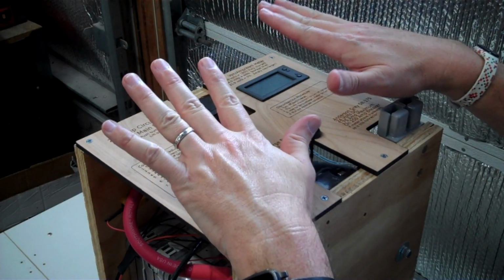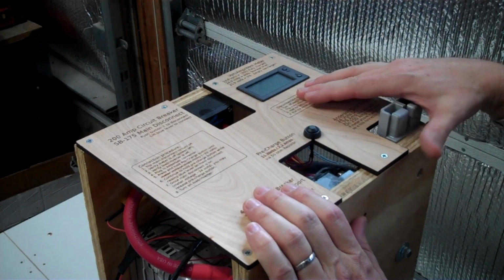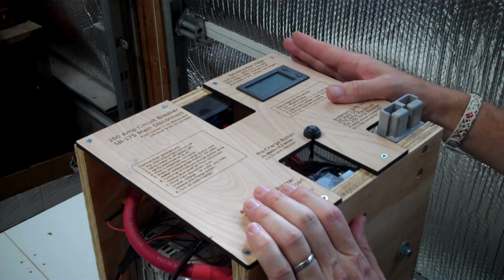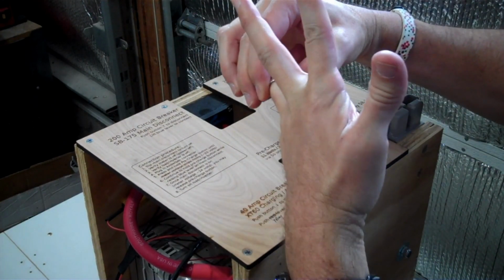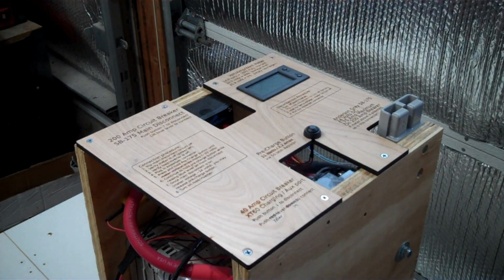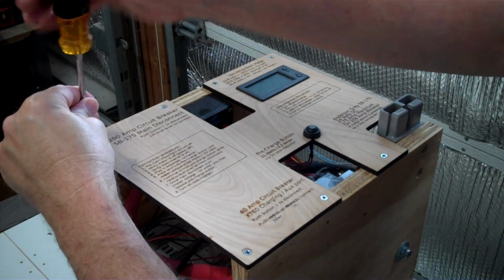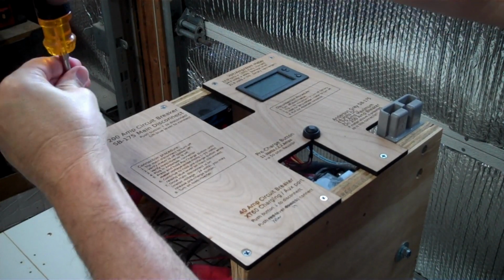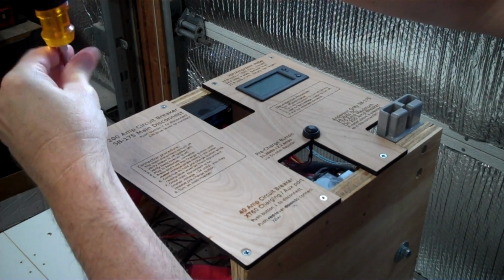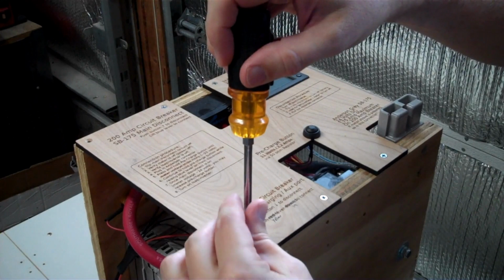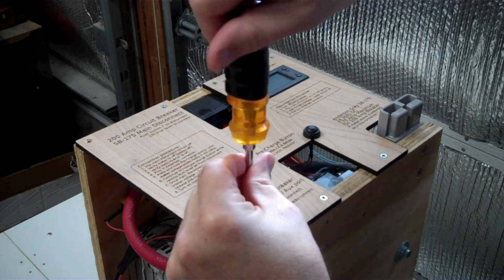So I'm going to be working around low voltage, only 24 volts, but a whole bunch of amps are in there. I'm taking off anything metal I have, like rings and watch bands, because if I were to bridge something, I don't want it sparking and welding itself and heating up really fast. Also, you don't want to drop screws down in your battery.